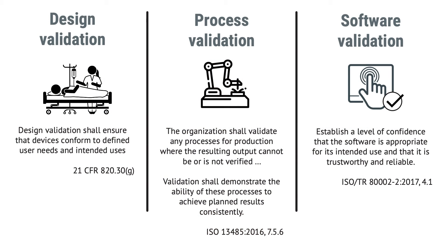Validation of computer software, or software validation, is about establishing a level of confidence that the software is appropriate for its intended use and that it is trustworthy and reliable. Requirements on software validation are found in both QSR and ISO 13485, and software validation would be required for software tools used to create or operate your software as a medical device.